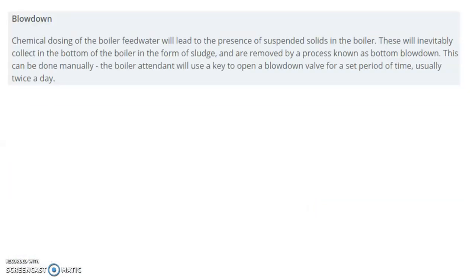Next is blowdown. Chemical dosing of the boiler feed water will lead to the presence of suspended solids in the boiler. These will inevitably collect at the bottom of the boiler in the form of sludge and are removed by a process known as bottom blowdown. This can be done manually — the boiler attendant will use a key to open a blowdown valve for a set period of time, usually twice a day.